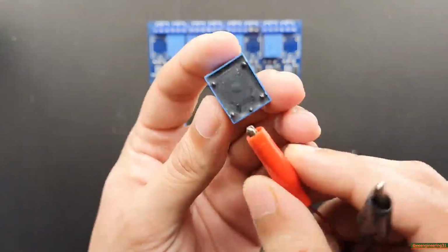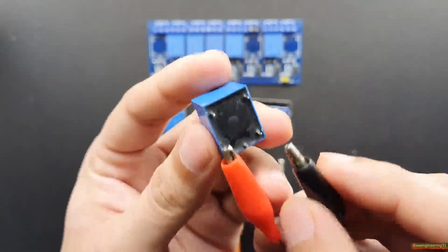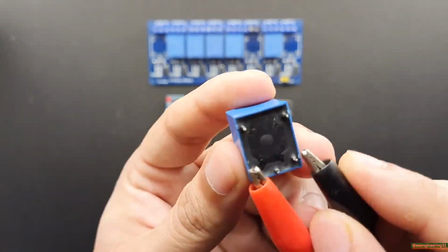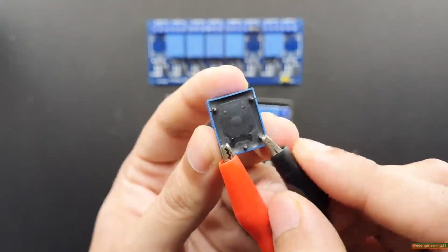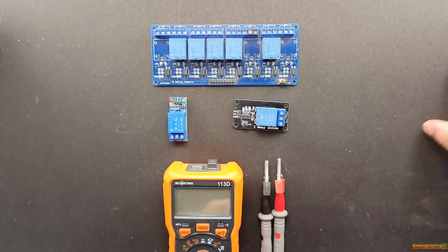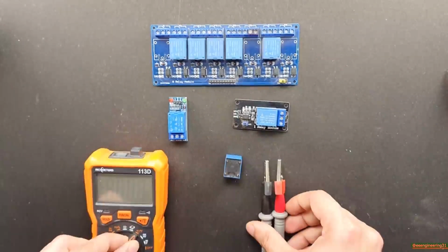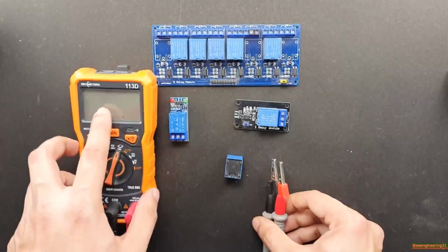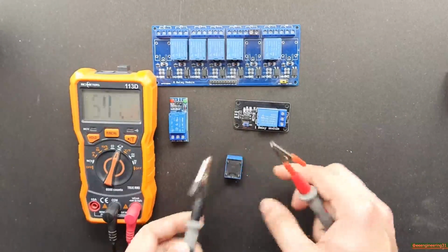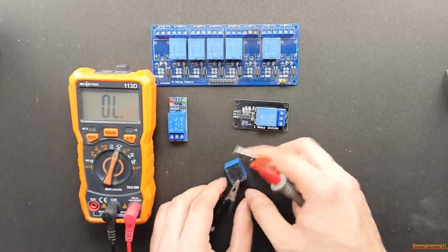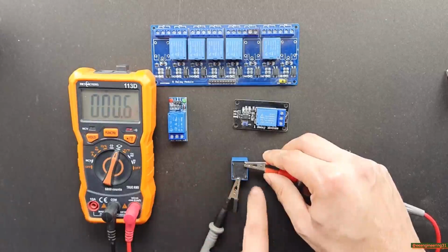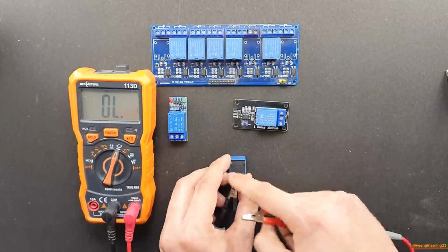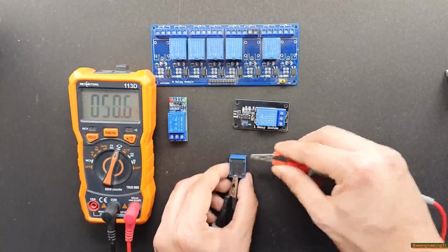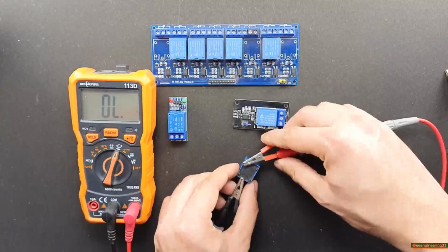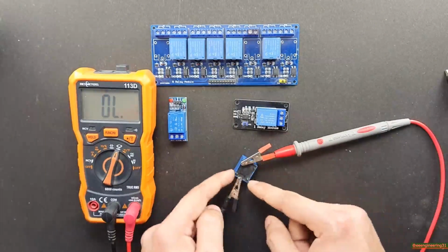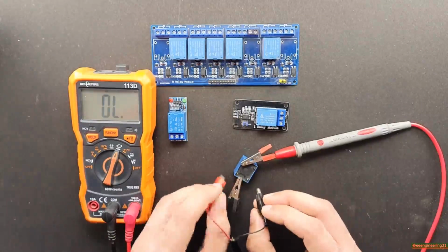Now let's check the same with another relay. Now I'll put the multimeter in continuity mode so that every time we touch it, it will beep. I will place one contact right here, and we can confirm this is the normally closed contact, because even when the coil is not energized, it is connected. And the other one is a normally open contact, so it will only connect when there is power applied to this magnetizing coil. So I'll apply power now.